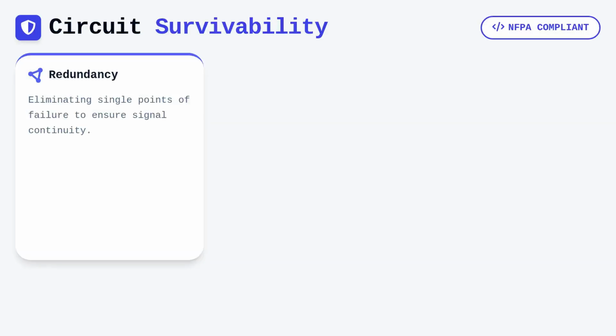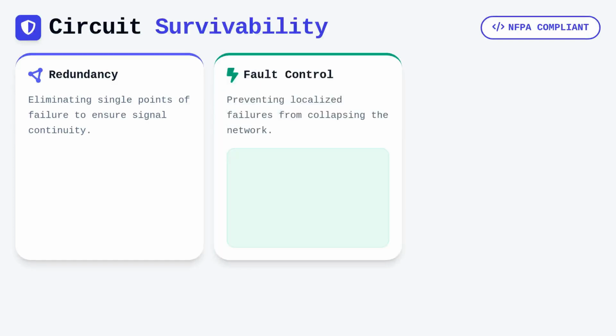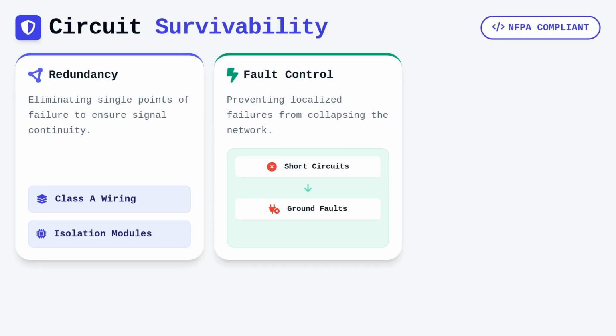Survivability is a critical dimension of our circuit design, as we must assume that parts of the building will become untenable during a fire event. NFPA standards mandate that we provide redundant signal paths so that a single fault, whether it is a short circuit or a ground fault, does not result in the loss of communication to an entire floor or fire zone. This is achieved through Class A wiring configurations or sophisticated isolation modules that disconnect compromised branches of the audio circuit while keeping the rest of the network operational.